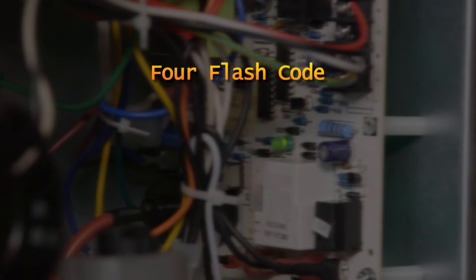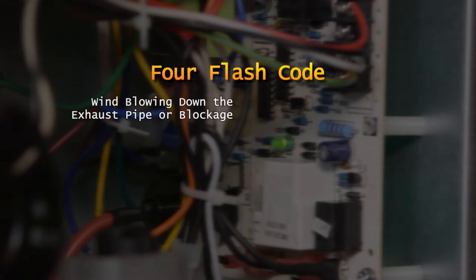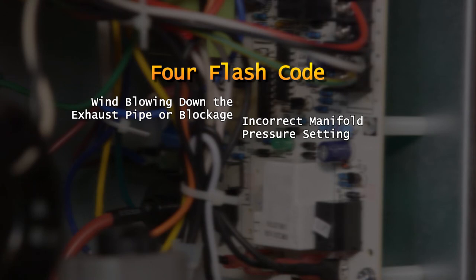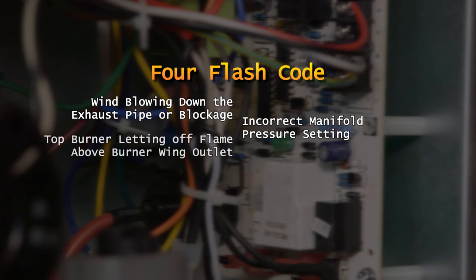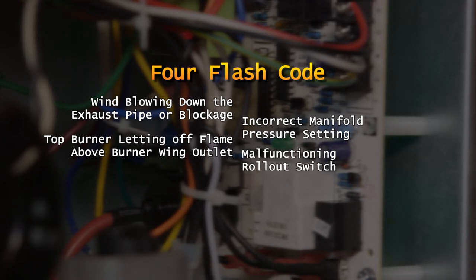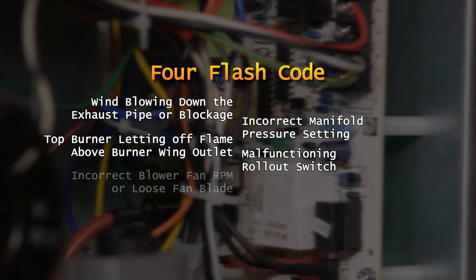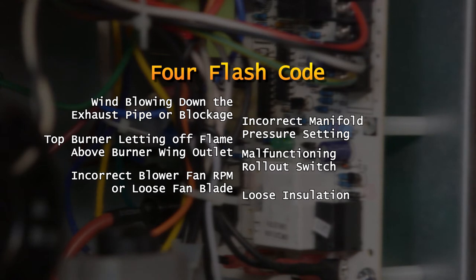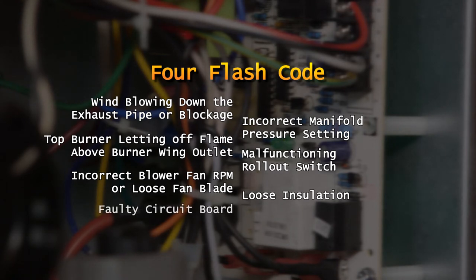The 4-flash code can indicate any of a number of problems. Wind blowing down the exhaust pipe or a blockage causing the flame to roll back into the burner area. Incorrect manifold pressure setting when converting from liquid propane to natural gas fuel. The top burner, letting off flame above the burner wing outlet, normally used to light the next burner in line. A malfunctioning rollout switch. Incorrect blower fan RPM or a loose fan blade. Loose insulation blocking airflow across the heat exchanger tube. A faulty circuit board.